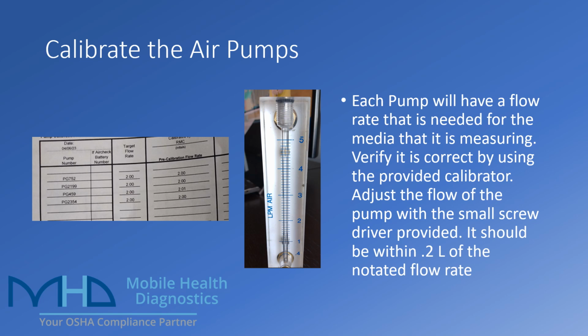The one pictured here in the middle is one of the manual ones, which is what we're going to demonstrate here. There's a digital version. Their function is almost exactly the same. You're also going to want the pump calibration sheet, and what you're specifically looking for here is both the targeted flow rate and what the pre-calibration rates were.